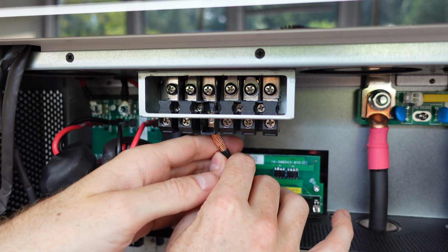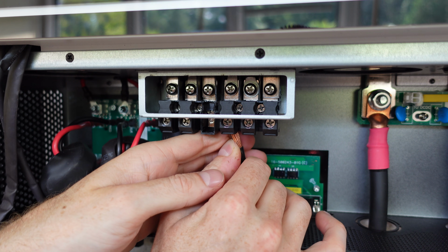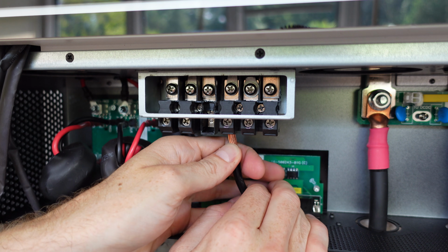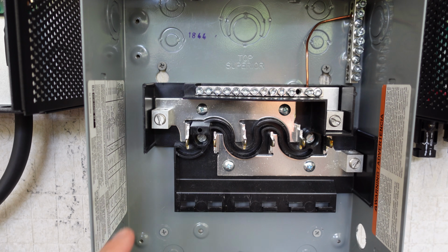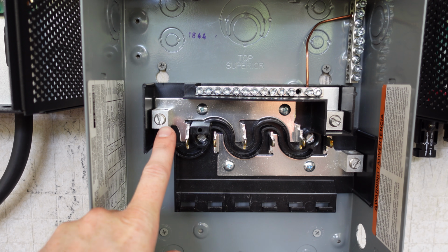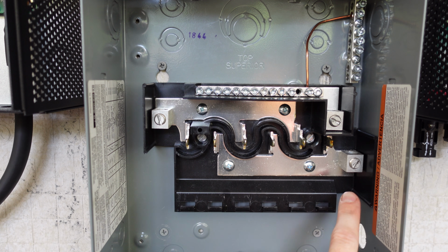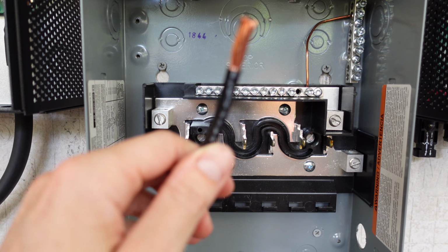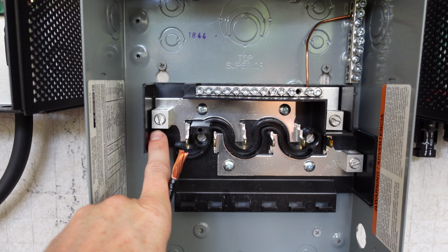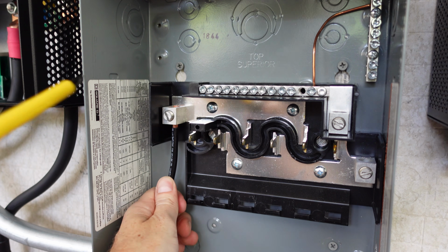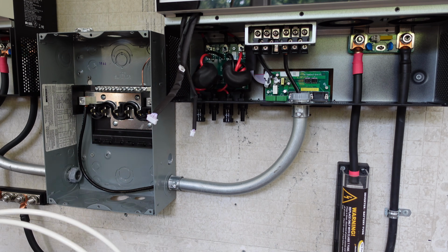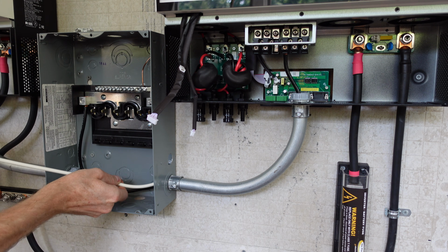But so the black wire is going in the terminal for the output marked L for line. So on the electrical panel, we have one lug for line 1 and one lug for line 2. So I'll just put the black wire on the first terminal to the left. And next we'll run the neutral the same way.